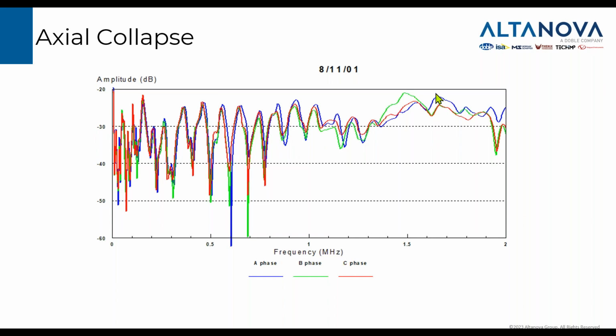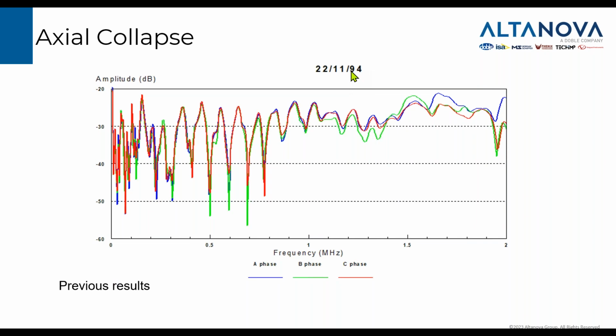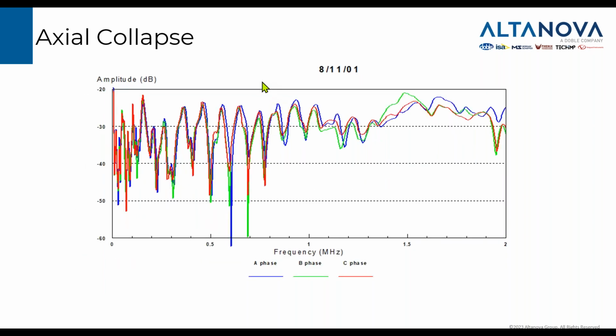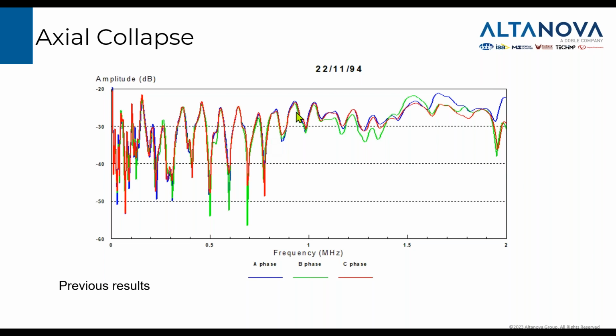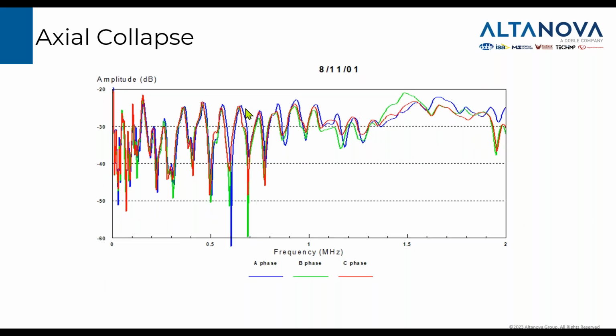Well, for this one, we had a reference from the past. This test was made in 2001 after the Buchholz alarm, and before that in 1994, the traces look like this. So if you look carefully, this is before, and that one was after. Basically the after results show this slight shift of the traces, and that gave us a hint that something is going wrong with A phase of this transformer.